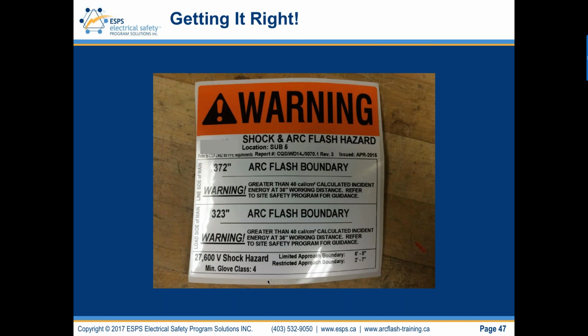This label is ambiguous. It doesn't tell me the incident energy. It just says it's greater than 40, right? The label should tell the worker what the incident energy is. The company's electrical safety program then advises what the qualified electrical worker will do based on the incident energy on the label. The company's electrical safety program should also dictate the specification for these labels and when danger is used versus warning in the signal panel.